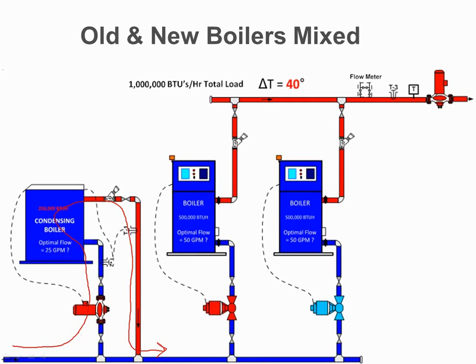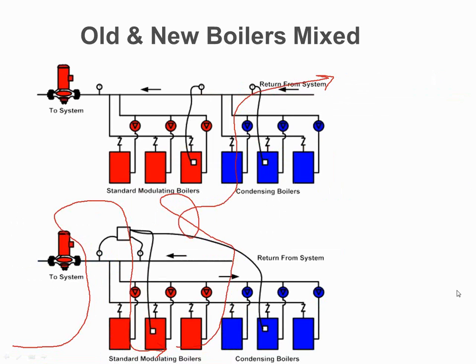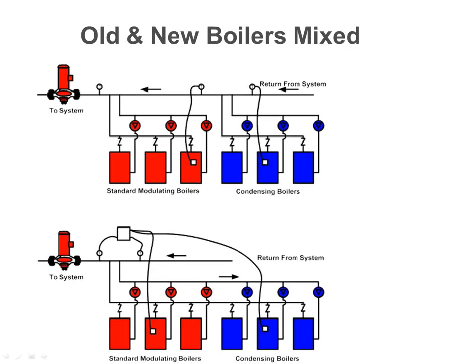When that condensing boiler can't keep up, when the temperature does get low enough, then it calls on the next boiler. Depending on how those are wired together, we'll call them next one or two, depending what's necessary. A lot of these condensing boilers have what I like to call the Dinosaur Switch, which basically calls that next boiler on when it can't keep up. Here are just a couple more methods of showing how to do it.